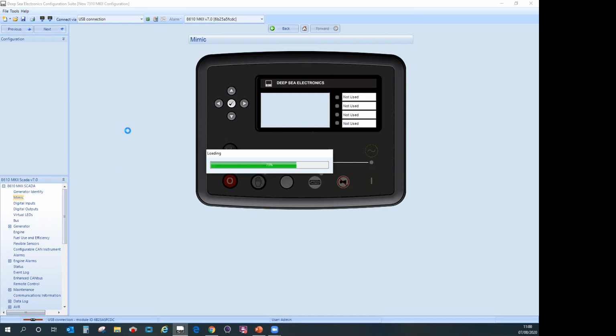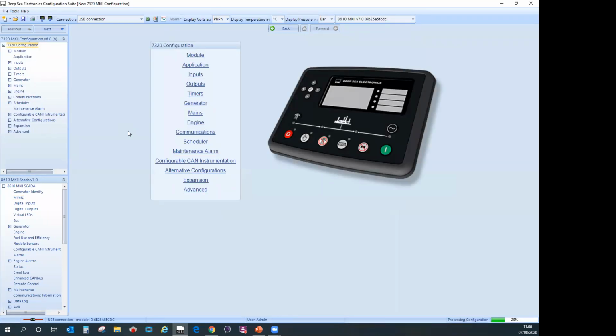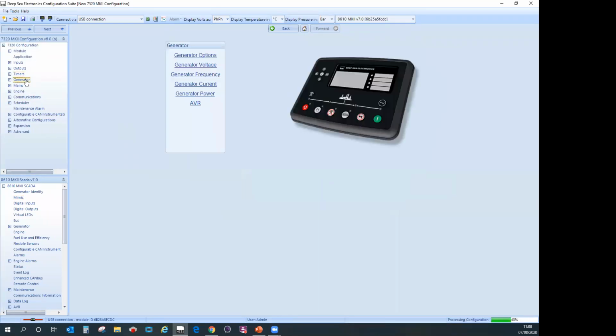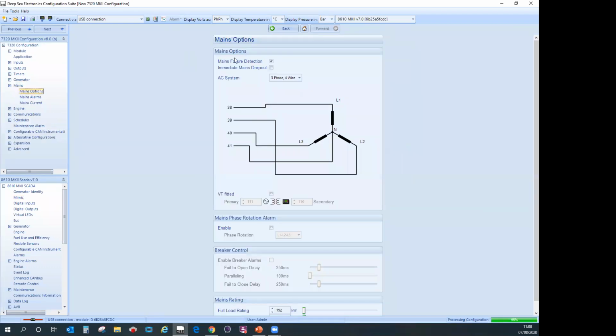Let that load up. So if we go to generator and mains options, you just turn off the mains failure detection, and that turns it off on the controller. What will happen then is the mains LED and breaker LED will be lit, and anything going on with the mains will just be ignored. So you're turning off the mains detection.